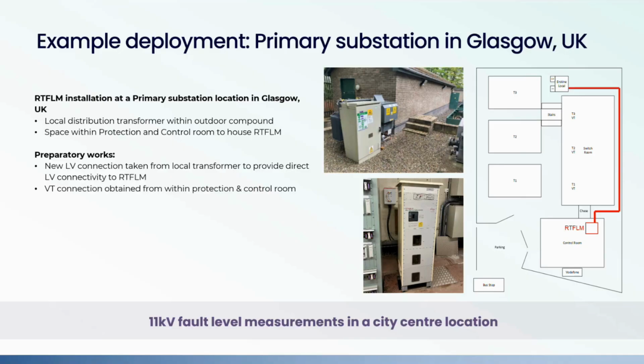That's where we connected the LV inductors, the LV disturbance generator, as we call it, and we were able to take a connection to the VTs for each of those primary transformers from within that protection and control room as well. The way our network is configured at this site is we have 3 primary transformers which all feed the same 11 kV bus bar system, so we've configured a connection from each of those VTs with a changeover facility should we need to change between one and the next.